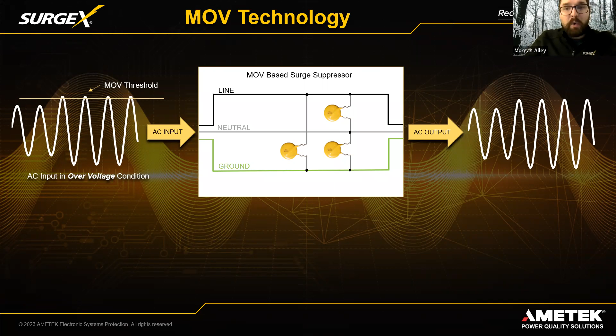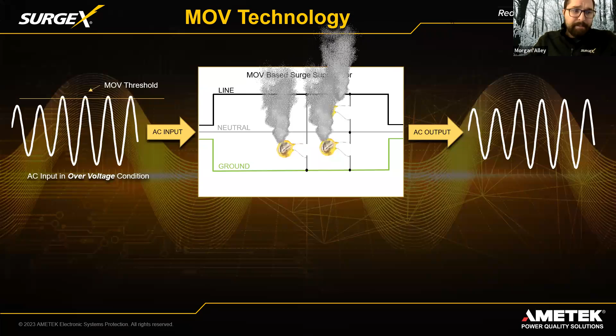MOVs can only be used for short surge protection. They can't handle sustained surges or overvoltage conditions. So an overvoltage is when that sine function doesn't have a drastic spike, but the peaks and the valleys are much higher and lower. So that's what overvoltage is. MOVs are not designed in any way, shape, or form to correct for overvoltage, which again leads to equipment damage. They also become permanently damaged, not leaving any protection for your equipment. So if you have a couple of surges or an overvoltage occurrence, the MOVs are going to burn out and not function after a certain point.